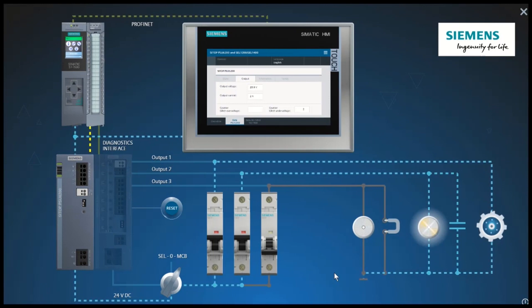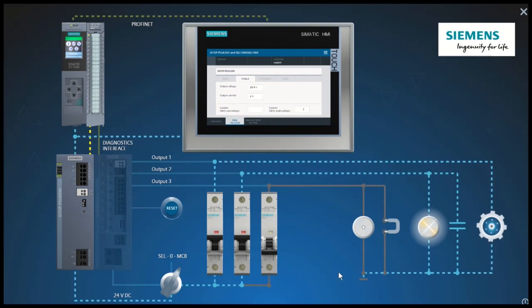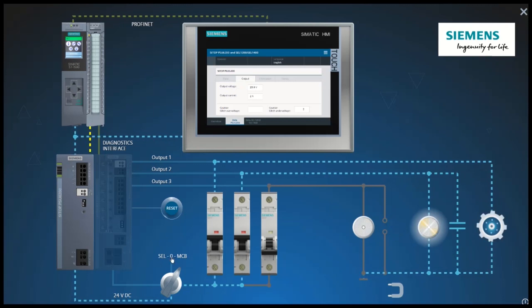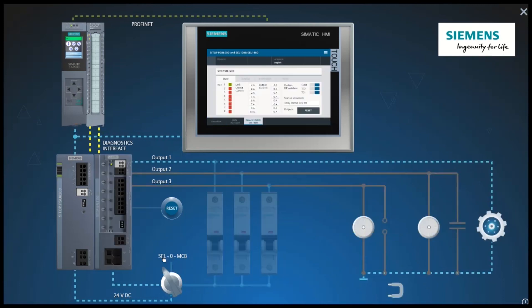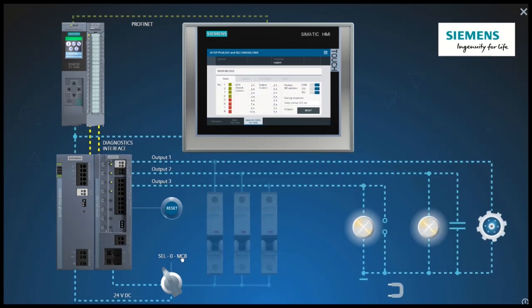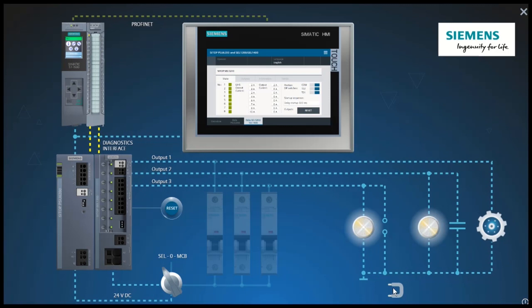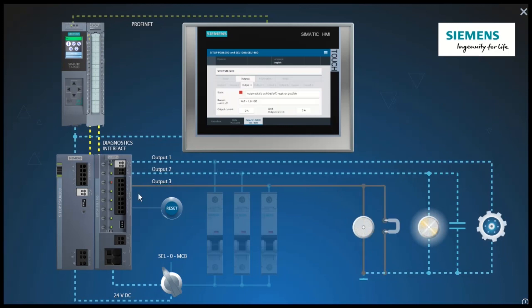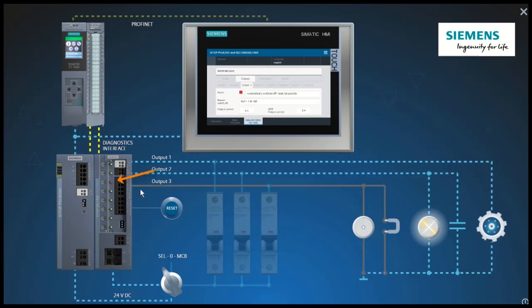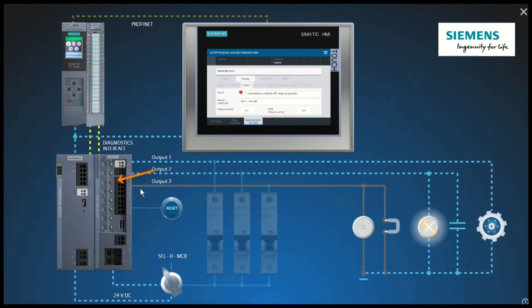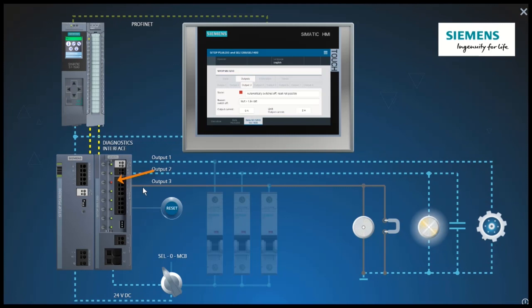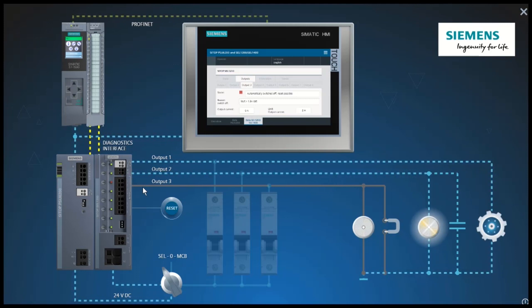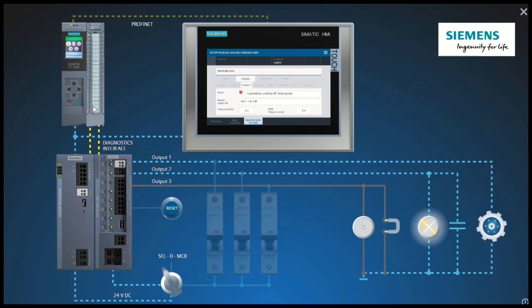Now we will also simulate a short circuit on the SEL 1200. The third output reacts immediately and switches off. The output voltage of the power supply remains stable and the PLC and the panel continue to run.